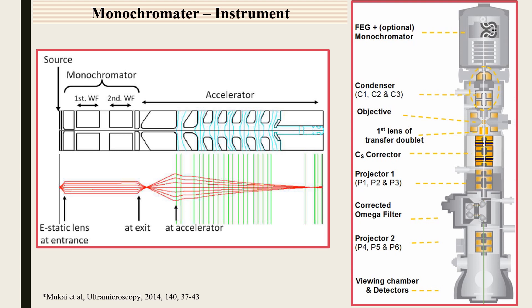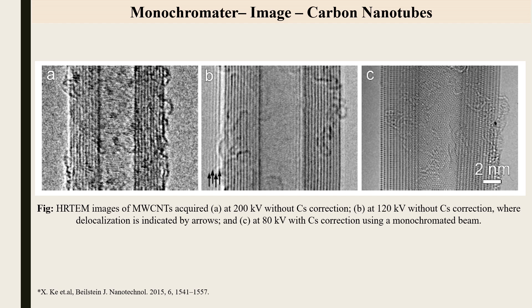The monochromator system filters the beam and minimizes energy spread. It is placed after the source and before the accelerator. For example, comparing image A imaged at 200 kV without spherical aberration correction, image B at 120 kV without spherical aberration correction — where delocalization is indicated by arrows — and image C at 80 kV with spherical aberration correction using a monochromated beam: comparing A and B, B is far better; and the third system with monochromated beam and aberration correction gives the best atomic contrast, for example around carbon nanotubes.